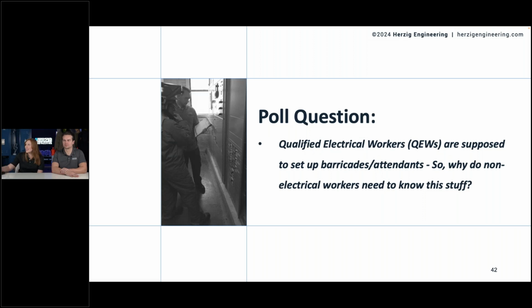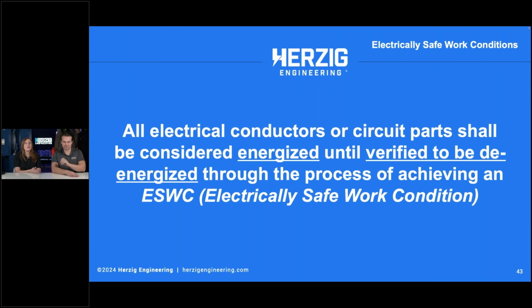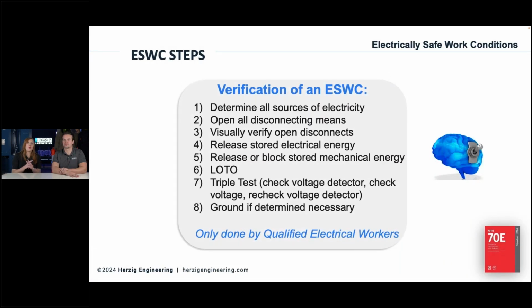Now another piece: I mentioned the authorized worker who does lockout tagout. Maybe they work on mechanical parts or pneumatics, whatever may have you, but there are electrical components in that same work environment. What they need to understand at that point is that all electrical conductors or circuit parts are considered energized until verified to be de-energized through the process of achieving what's called an electrically safe work condition, ESWC.